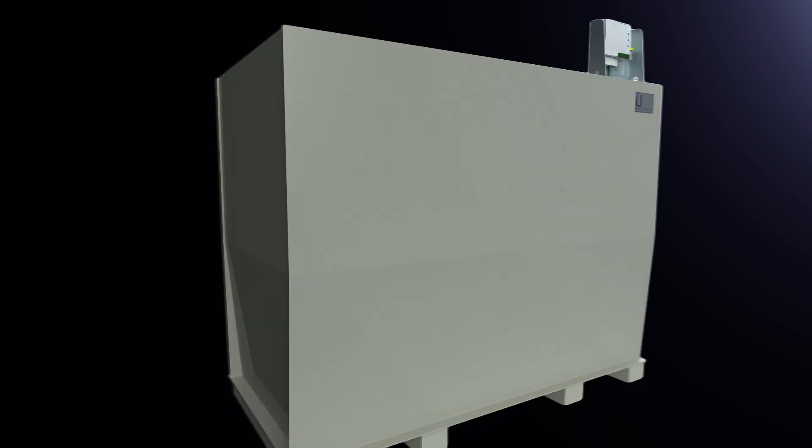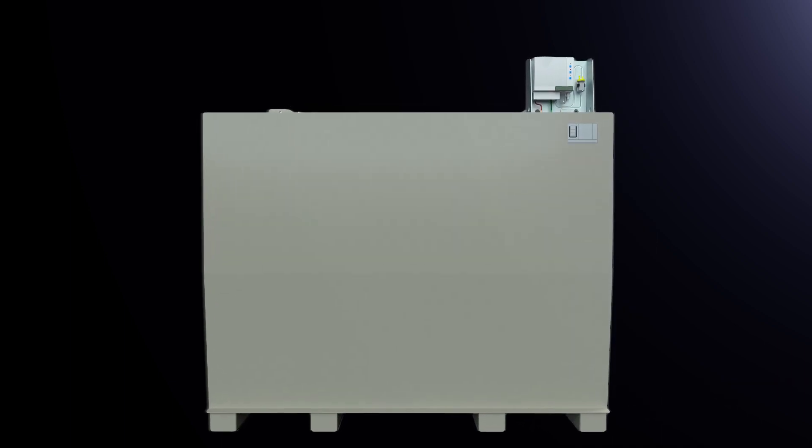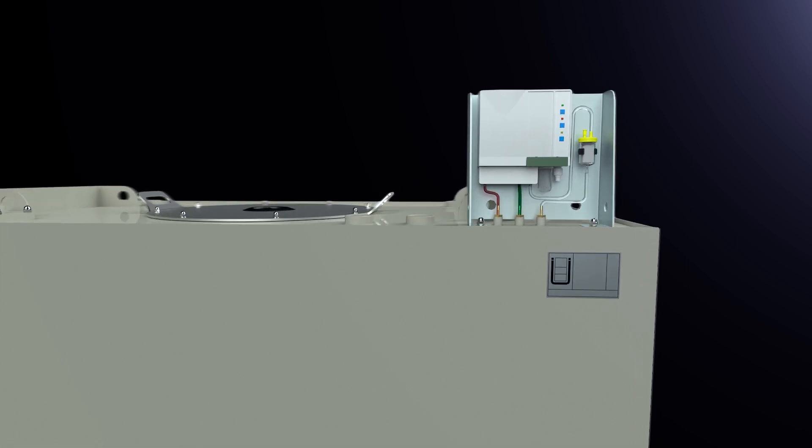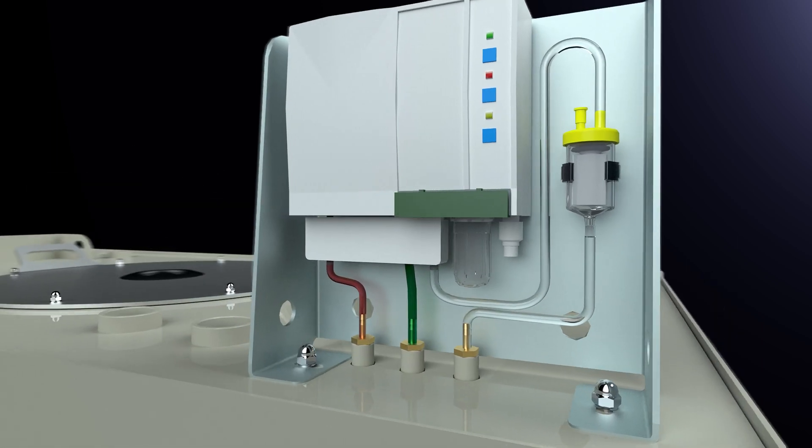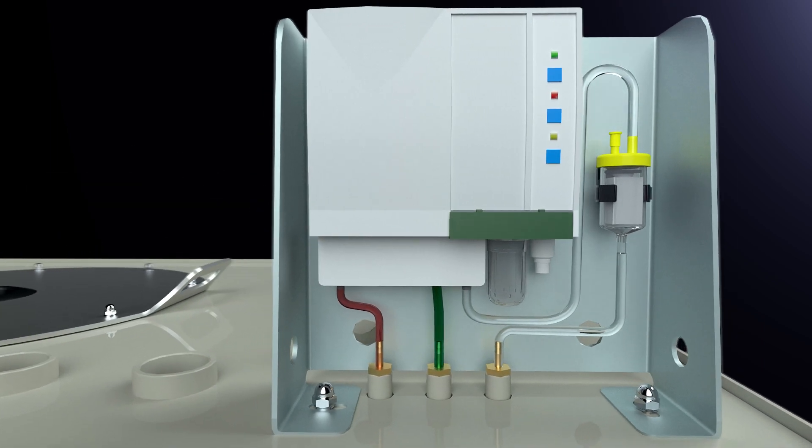A vacuum leak detector constantly checks the tightness of the tank. If the tank leaks due to corrosion or external damage, the leak detector triggers an alarm.